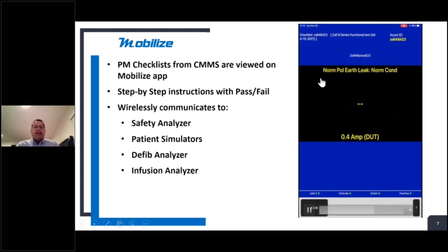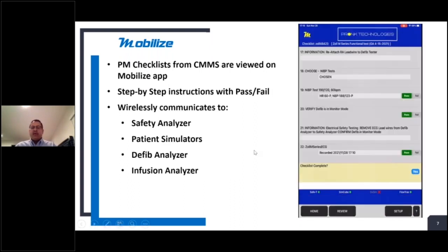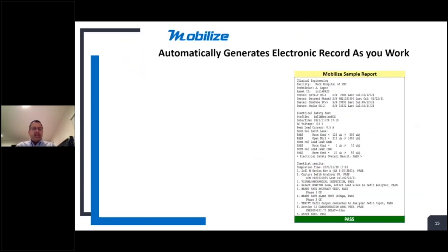So it automatically goes to the safety analyzer and it says, let's run these series of tests. It's executing each one of the tests. In the center here, it's the measured values in terms of the leakage, and at the bottom here, it's displaying how much current draw the device under test is drawing during these tests. So I have executed a bundled test of electrical safety tests to run. It's going to automatically do that, and without the technician having to do any interaction, that information is being captured. So it allows me to really see and capture everything and have a complete test report.